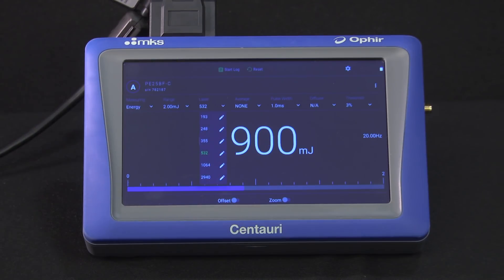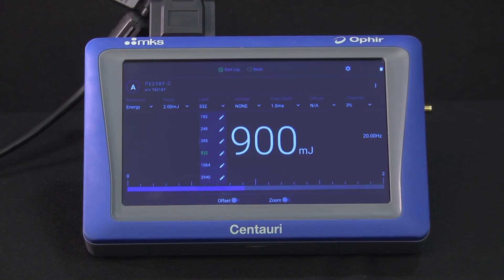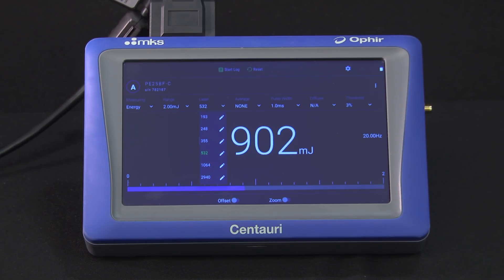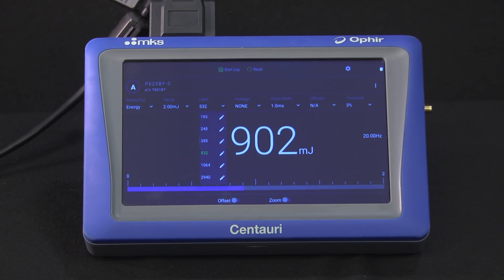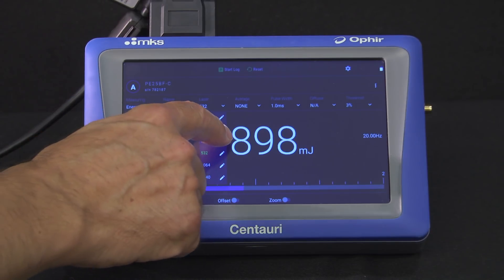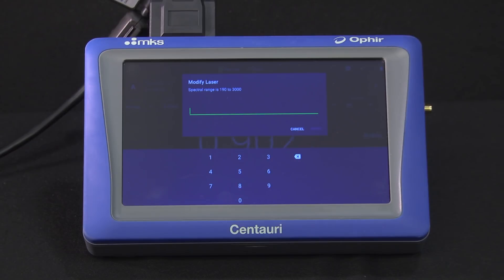Laser or Wavelength. Depending on the type of absorber used in your sensor — such as Metallic or the broadband BF or BB absorbers — there might be just a few discrete wavelength settings, or, as in this example, a full curve with the option to edit any of the default favorites to any other wavelength in the sensor's specified range.